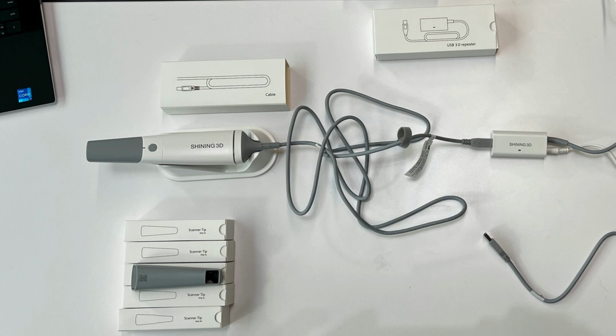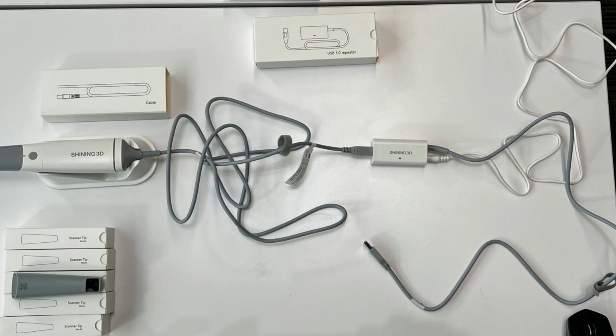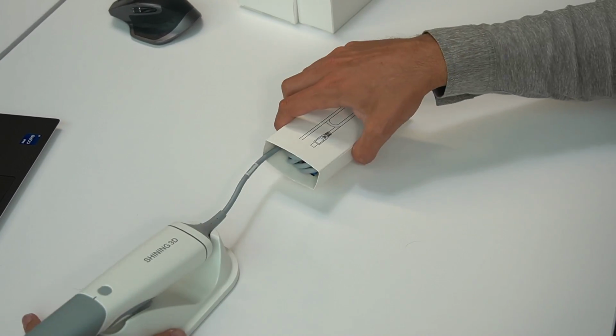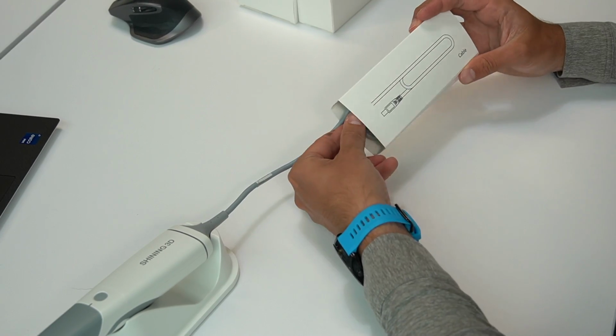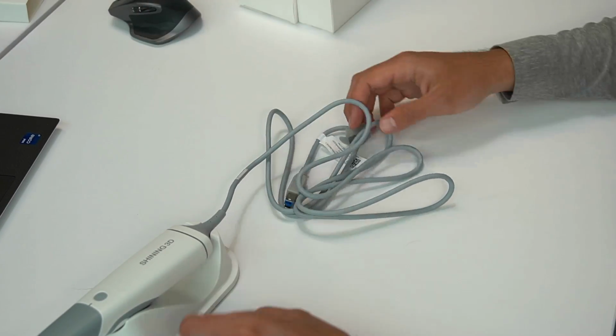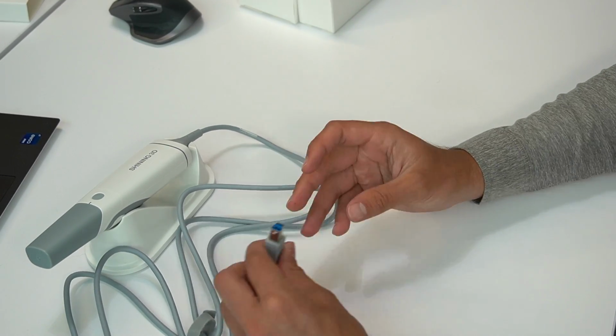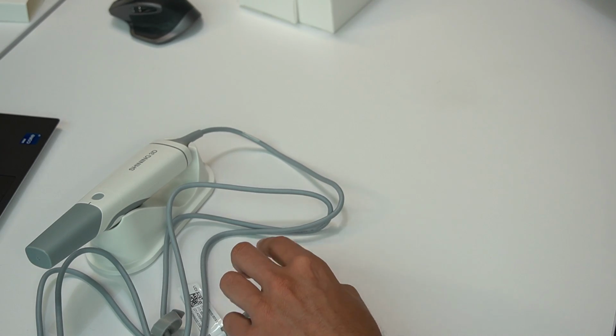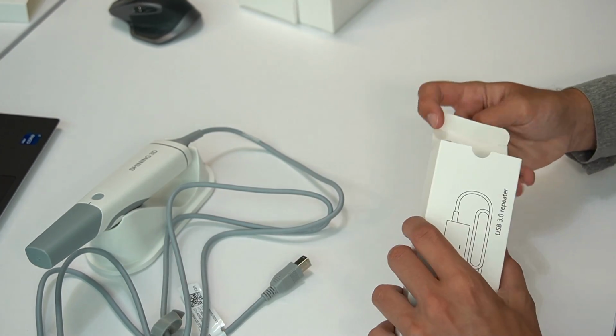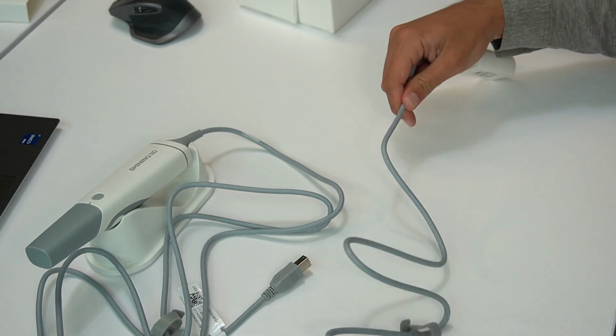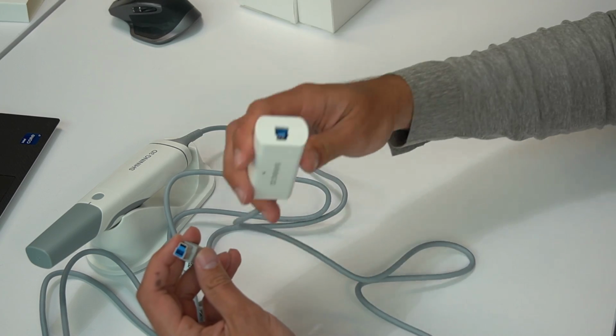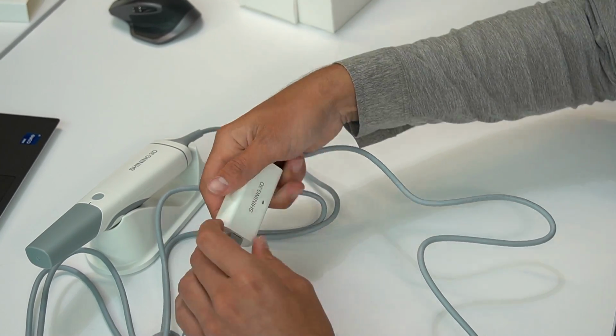So you want to connect your scanner to the repeater. You want to connect the repeater to the adapter, and then you want to connect the repeater to the computer. If we look at that from a logistical point of view, always start with your scanner. So I will take the scanner cable out. The scanner cable is going to plug in to your repeater. You'll notice the blue end of this scanner cable is going to plug into your repeater. So blue to blue, and it only will go in one way.